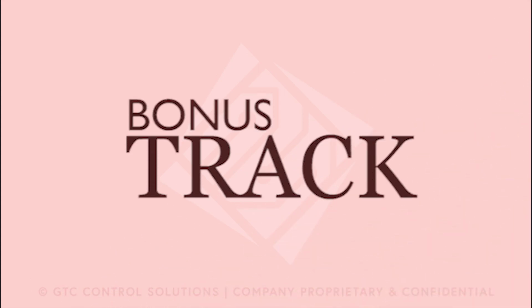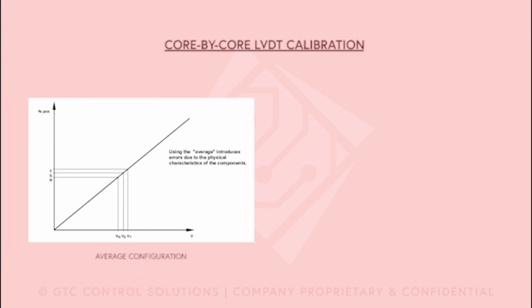We finally arrived to the last slide, the bonus track. When in Mark V units, you calculate the average of the results of the calibration and input that average to all three cores, you're introducing an error. This is what's happening. Each core reads its own voltage because it has its own physical components, capacitors, resistors, the things that read the voltage coming from the LVDT, and translates that with an offset and a gain into a position. And you can see here, if you use the average, each core will calculate its own position. And they're sometimes quite different, perhaps even 1% difference or more.